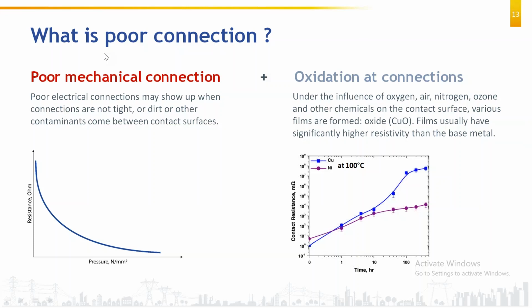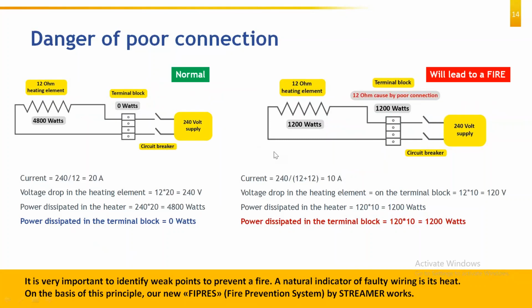Okay, so we have seen two issues. One is a mechanical connection where you have a nut bolt or bus bar tightened on a connection, and second, the circuit breaker contacts which are making and breaking. Both have the common issue of the loose connection. If there is a loose connection, there will be localized overheating and eventually your contacts will burn. So we will try to understand this scenario with an example, which is shown here.